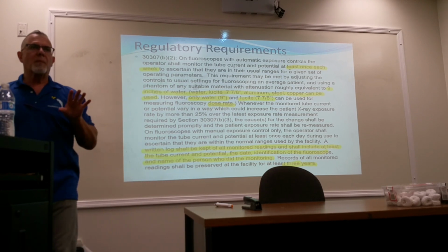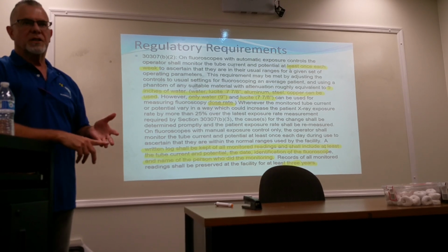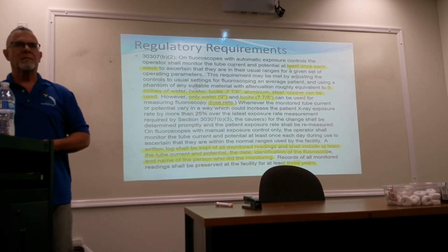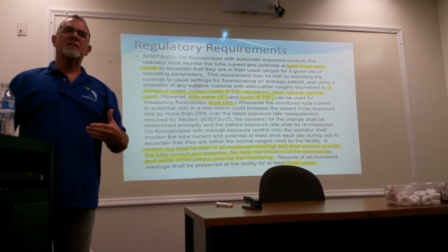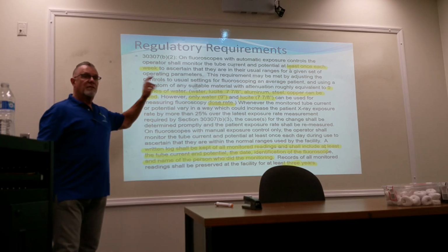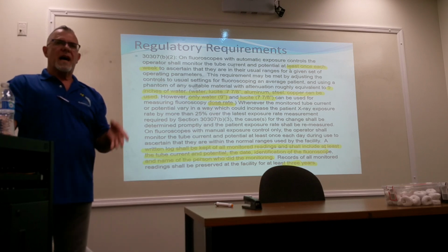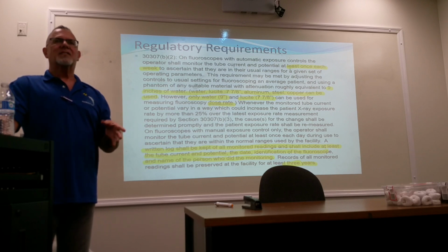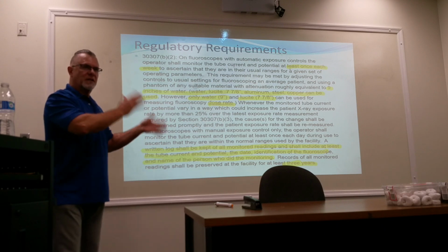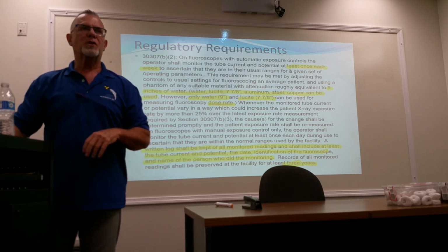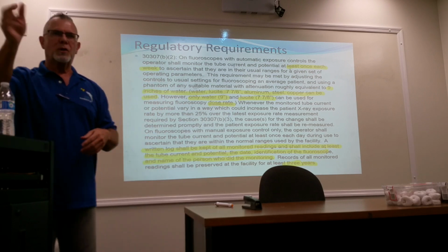Where that comes into a problem is we have X-ray equipment everywhere. Radiology, urology, surgery, cardiology, pick an ology, and they all have X-ray in them. What the facility has to determine is who's going to take responsibility for that weekly check. In some facilities, the night X-ray tech gets to do it, and every night of the week, they do a certain set piece of equipment, and they just keep doing that in perpetuity. In some facilities, no. Radiology says, hey, we'll do our equipment, you have to do yours.